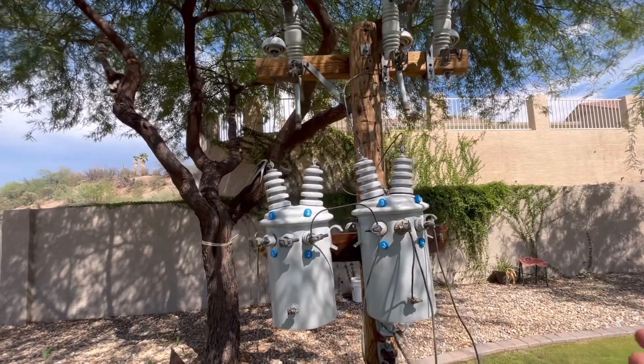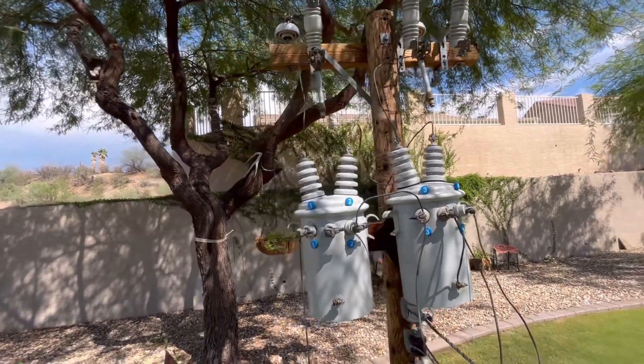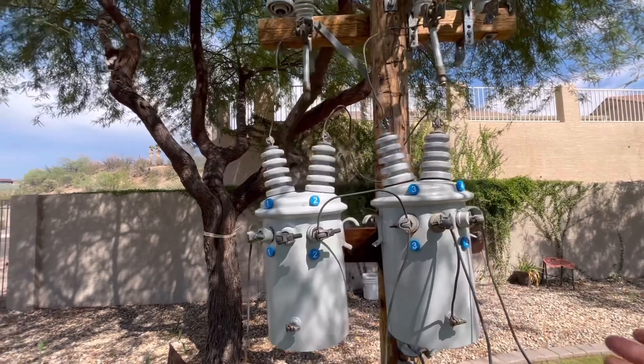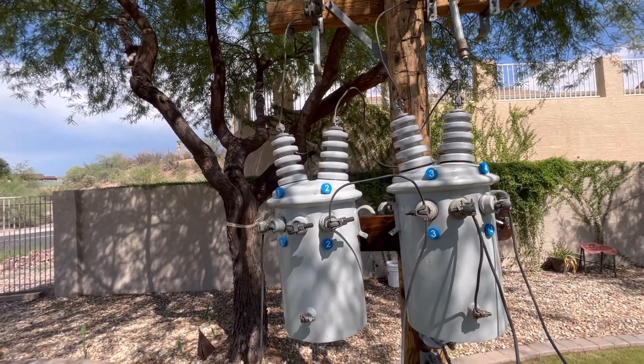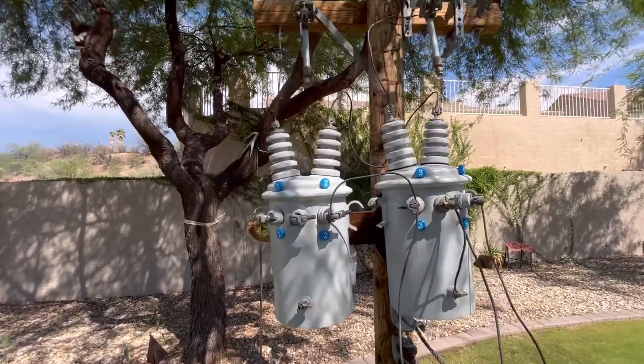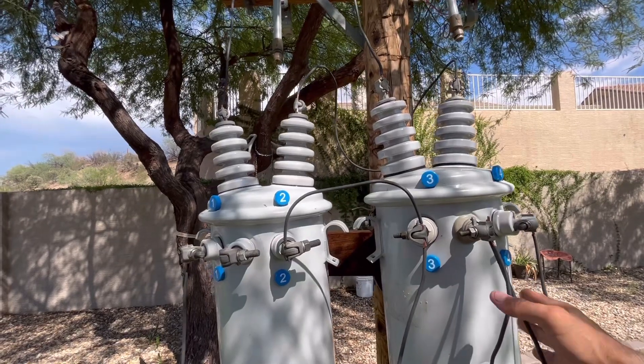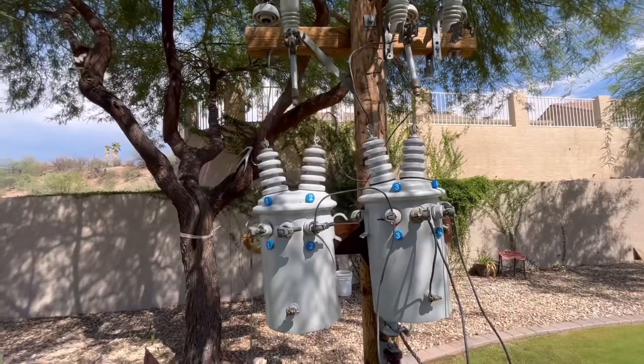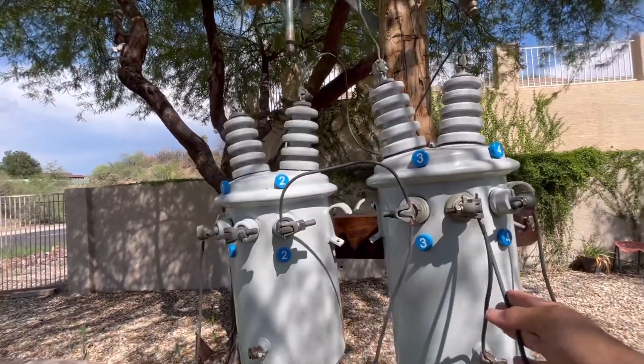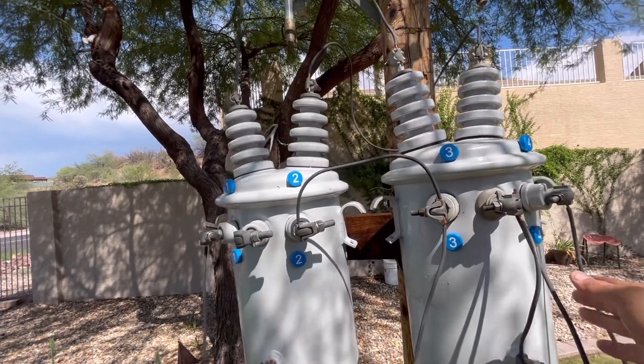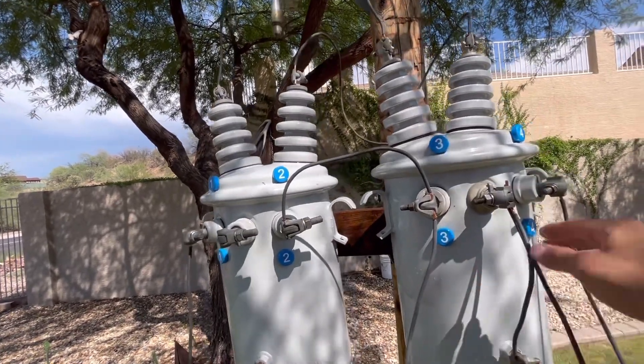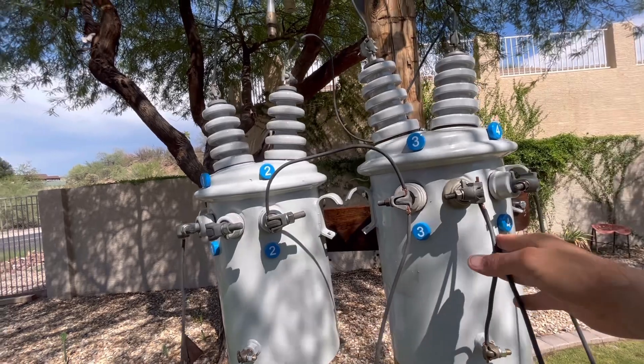So when it comes time to energize this bank, there's a certain procedure we want to go through in order to make sure that this bank is loaded in the proper way. So what you want to do is you want to energize your light pot first. In energizing the light pot first, you're going to energize and put the phase-to-neutral load, or the lighting load, on the transformer bank first.